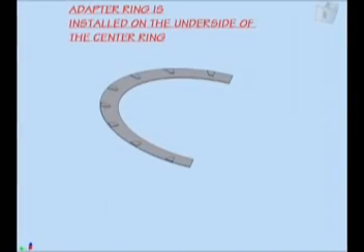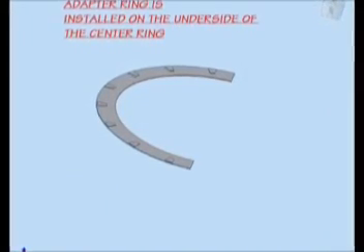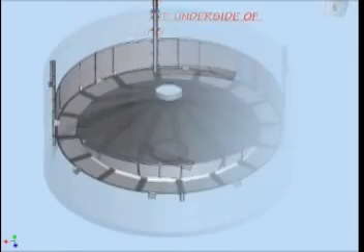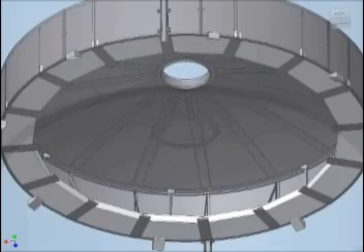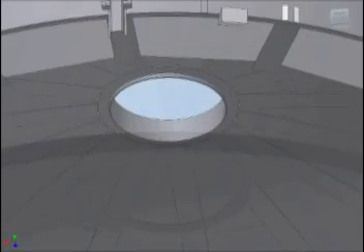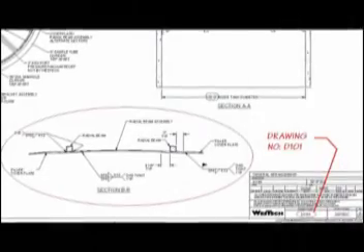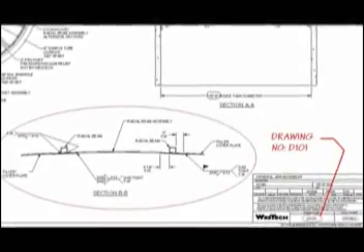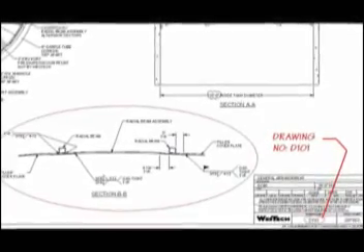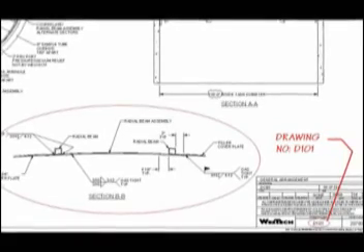Use a back step or skip weld sequence procedure to distribute heat and prevent buckling. All continuous welds must be gas tight. Strictly observe the welding symbols on the Westech General Assembly drawings.